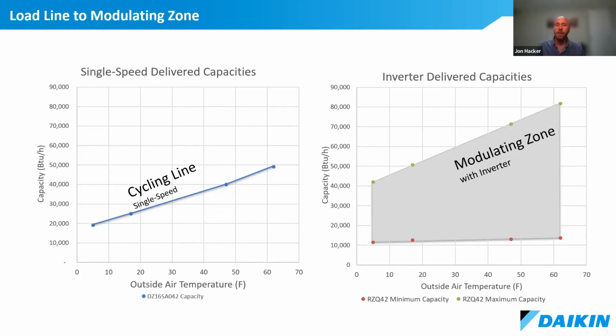And that's important. Moving over to the right-hand side of this slide, I'm showing a very similar product. It's also a 3.5 ton, centrally ducted product, but this is a heat pump with an inverter. We no longer have a cycling line, but we have a modulating zone. That zone is shown in gray. It's defined by the bounds of the maximum capacity, shown by some green dots towards the top of that gray box, and the minimum capacity, bound by the red dots at the bottom of the box. The change from a cycling line to a modulating zone cannot be overemphasized. This has enormous impacts on the operation of the equipment, how it provides comfort, and its efficiency.